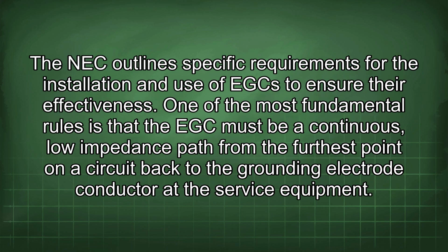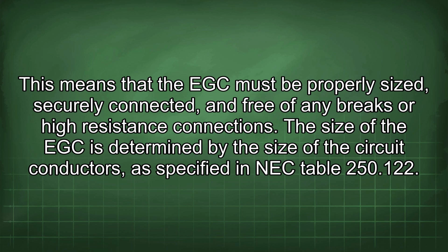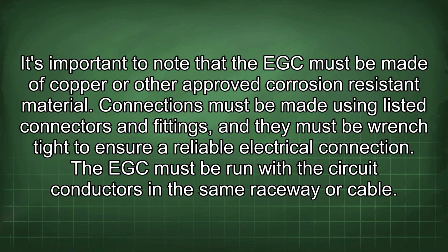The NEC outlines specific requirements for the installation and use of EGCs to ensure their effectiveness. One of the most fundamental rules is that the EGC must be a continuous, low impedance path from the furthest point on a circuit back to the grounding electrode conductor at the service equipment. This means that the EGC must be properly sized, securely connected, and free of any breaks or high-resistance connections. The size of the EGC is determined by the size of the circuit conductors, as specified in NEC Table 250.122. It's important to note that the EGC must be made of copper or other approved corrosion-resistant material.